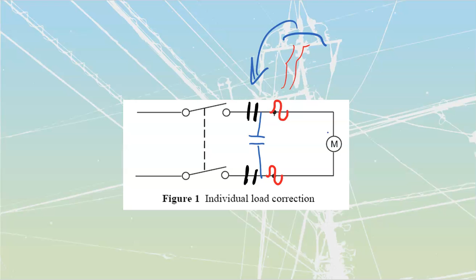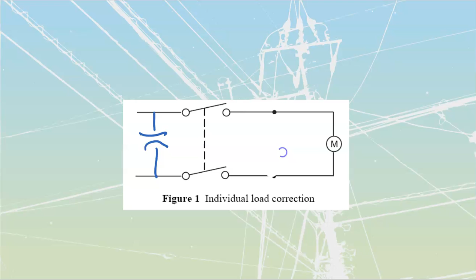I see that my cap is only going to be online when the motor is online, and offline when the motor is offline. You would not want to place it over here. If you did, then as soon as I switch the motor off, I lose my inductive vars, which means I could go into an overcorrected leading power factor and raise my terminal voltage values.